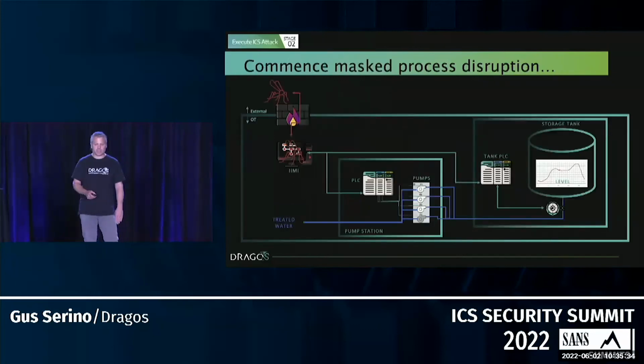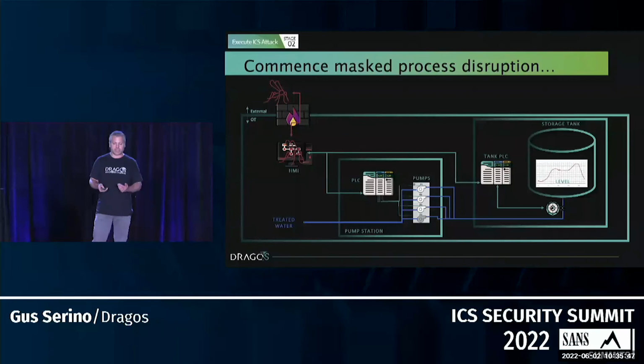And this is a really simple version of a water system. You see on the right a storage tank. The level in that tank is measured by that pressure instrument at the bottom. That instrument reports the level, and the HMI is polling that. We see the PLC here in the pump station that's controlling the pumps that are filling that tank up. Those PLCs are probably talking to each other as well as the HMI.